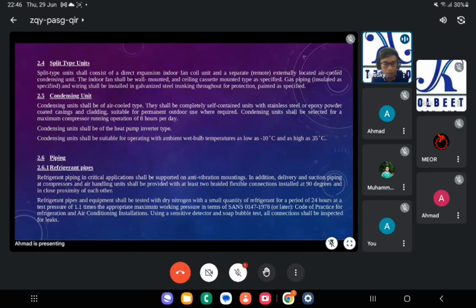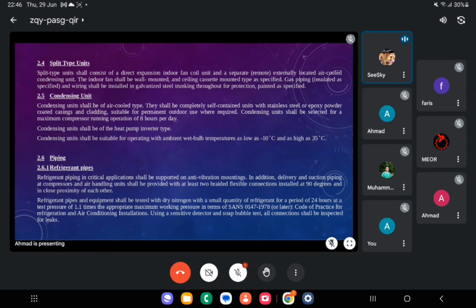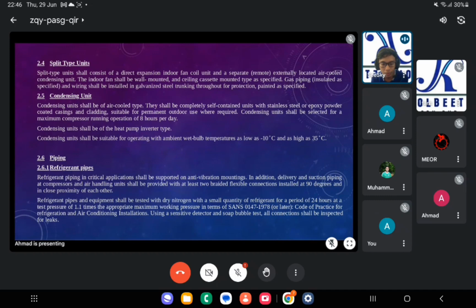Refrigerant pipe and equipment shall be tested with dry nitrogen with a small quantity of refrigerant for a period of 24 hours at a test pressure of 1.1 times the appropriate maximum working pressure in terms of SANS 0147 1978 or later, code of practice for refrigeration and air conditioning installation, using a sensitivity detector or bubble test. All connections shall be inspected for leaks.